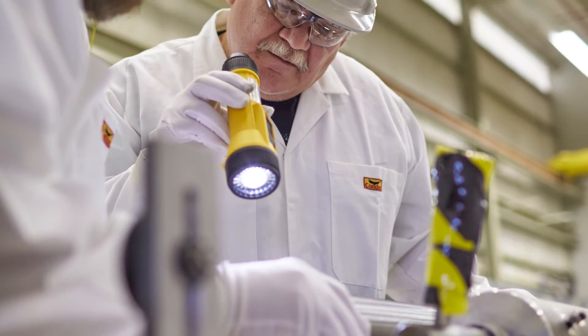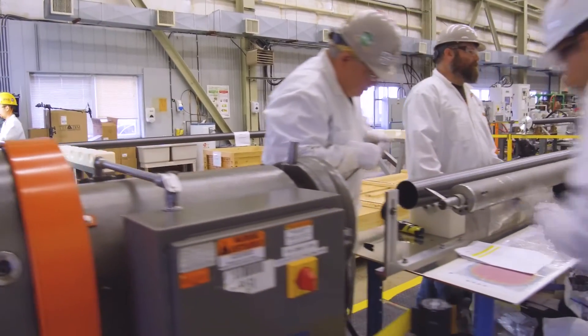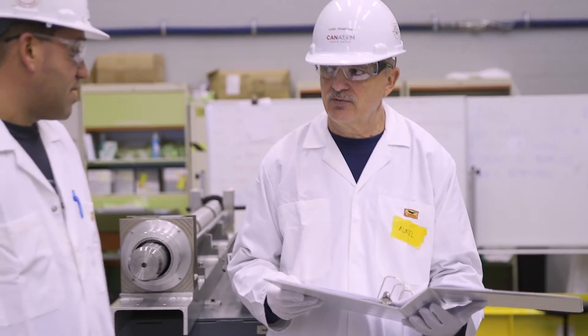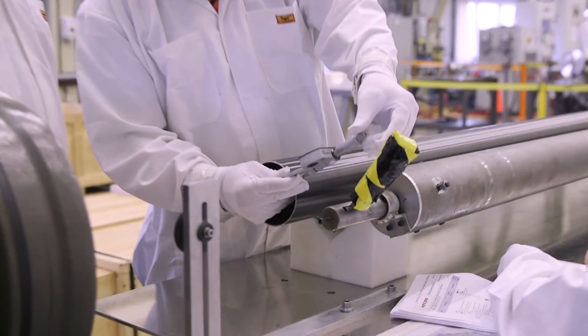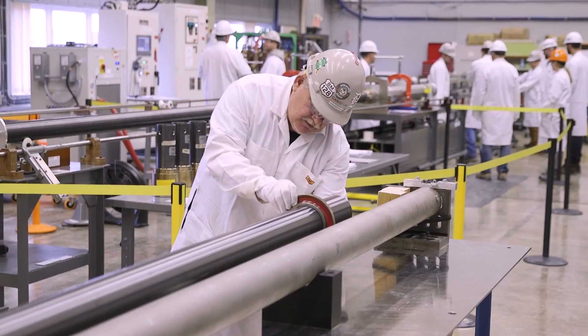This includes environmental controls to align with station requirements. The production of a fuel channel subassembly starts with the allocation of components being directly serialized to a specific location in the reactor. Once those components are identified, pressure tubes are cut to length and then inserted into an end fitting. Once this is completed, we perform the roll joint. Once the roll joint is complete, we do leak testing on the joint. Throughout all this process, there are many quality witness points and hold points within our inspection and test plans.